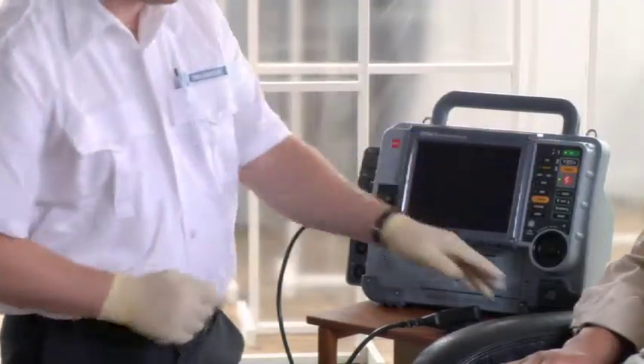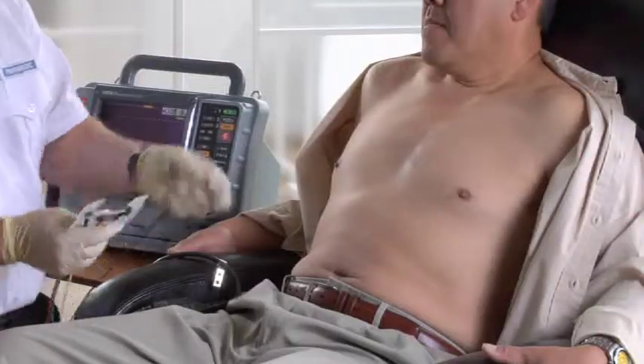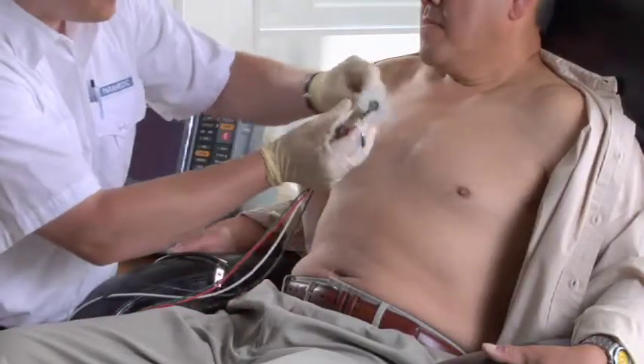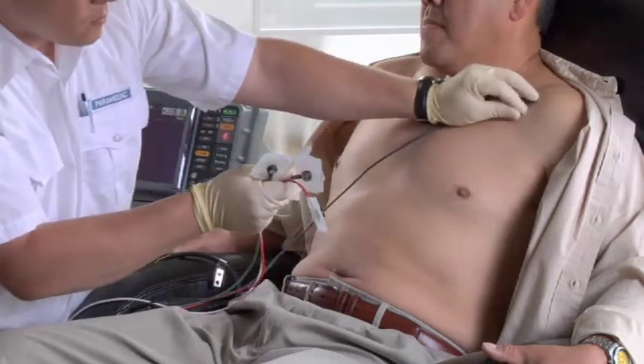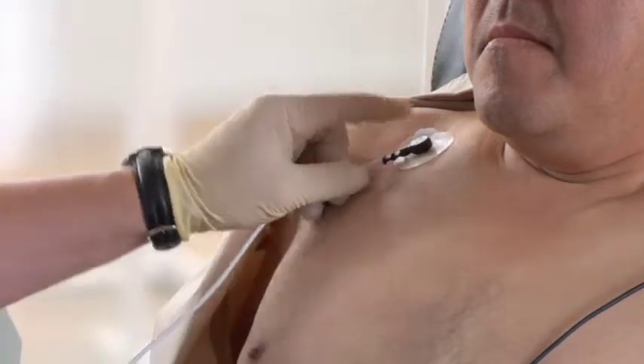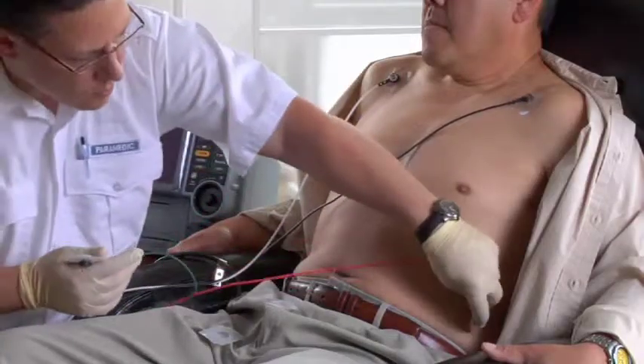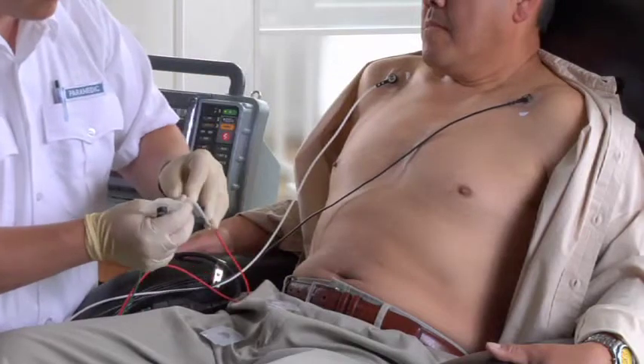Now the electrodes. You've probably gotten by applying ECG electrodes without skin prep, and the tracing was okay, but more likely than not, noise is going to be a problem. You can save yourself a lot of time by following these basic recommendations to decrease noise. Put the electrodes on the lead wire first before you apply them to the patient. Choose a site with minimal hair, or shave the site. Scrape the skin like this with the electrode backing to remove dead skin cells.